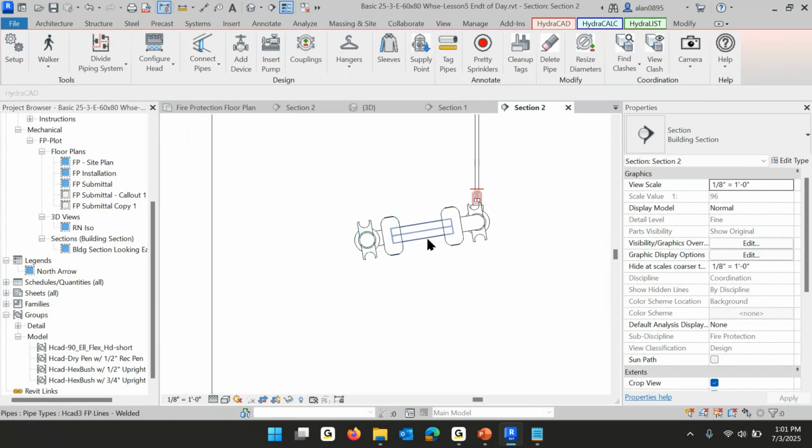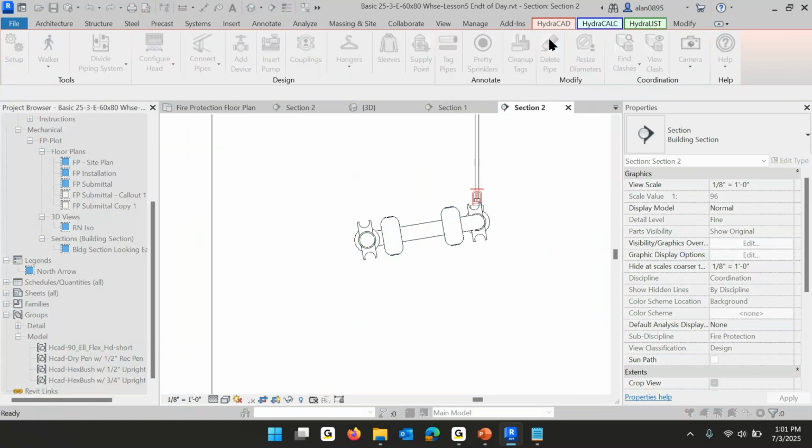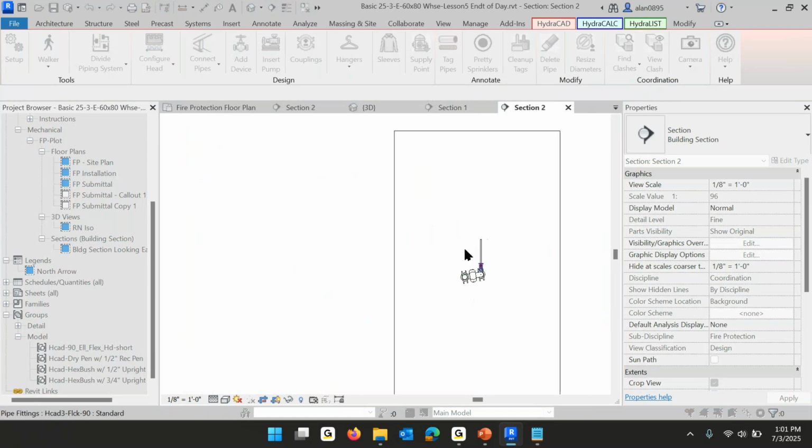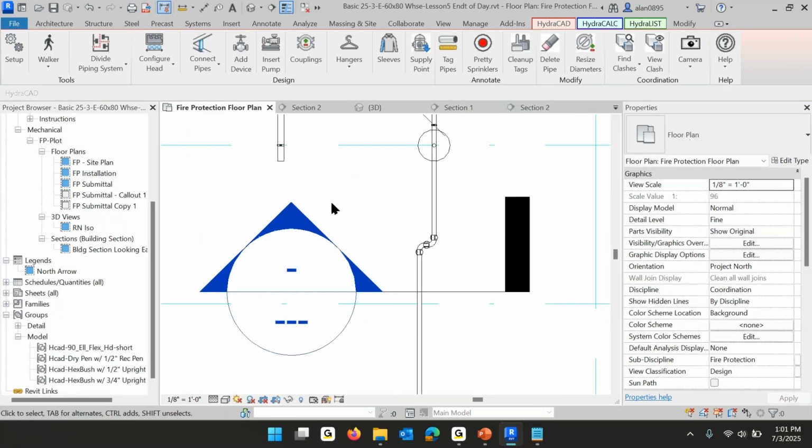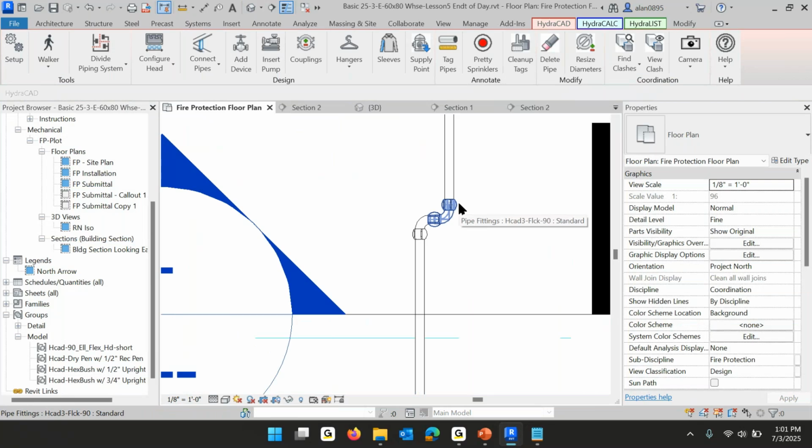If I deleted this pipe, I'd be offsetting just back-to-back elbows' worth. So there's a delete pipe between this fitting and that fitting. We used that in the riser, remember? Now I'm not at 18 foot 10 anymore, but I've got a rolling back-to-back elbow. Awesome. And if you wanted to do back-to-back 45s for some reason, you'd just do that in the section view, largely. Yeah, yeah.